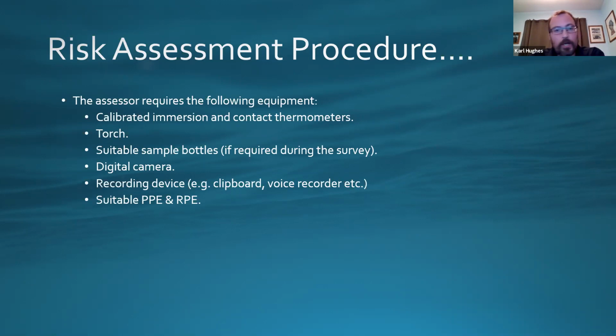A torch is needed for looking into cold water storage tanks up in roof spaces and things like that, just to see the internal conditions, and to follow any pipework. Suitable sample bottles are needed too - a couple of times on site I've seen things I think I need to action straight away, so you take a sample to be sent off to a lab for Legionella testing. A digital camera to show evidence of what you're seeing on site. Recording devices - I'm retro, I use a clipboard and walk around, but people have used voice recorders too, just to make sure you cover everything. Suitable PPE as well, make sure you're wearing your hard hat, hi-vis, etc., whatever the site tells you that you should be wearing.